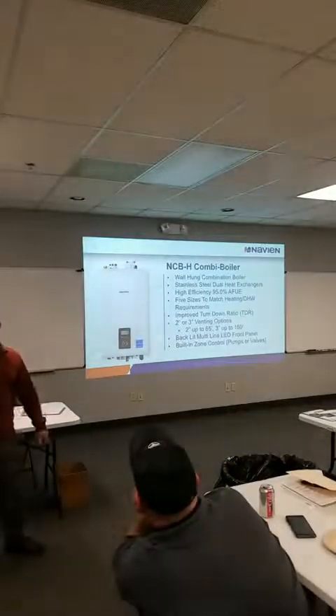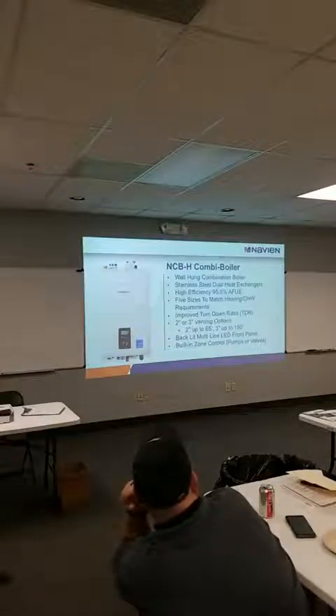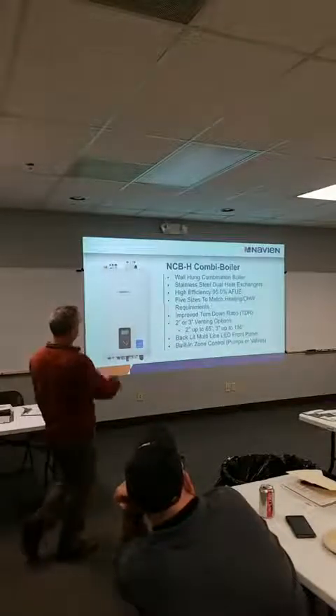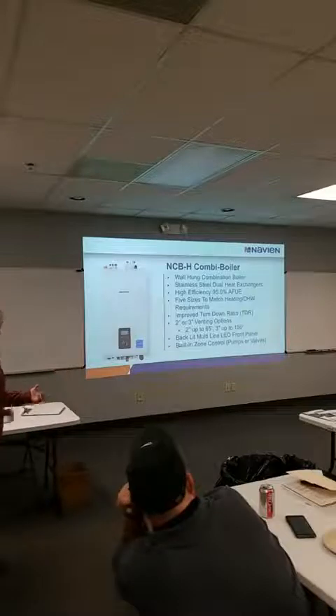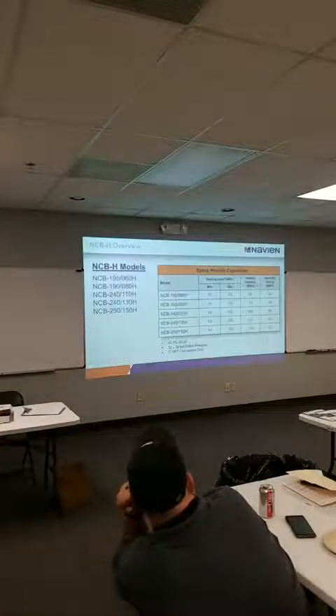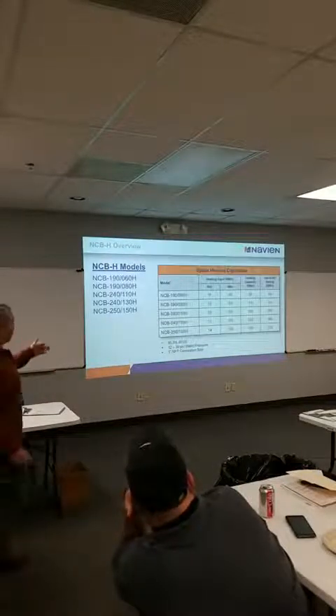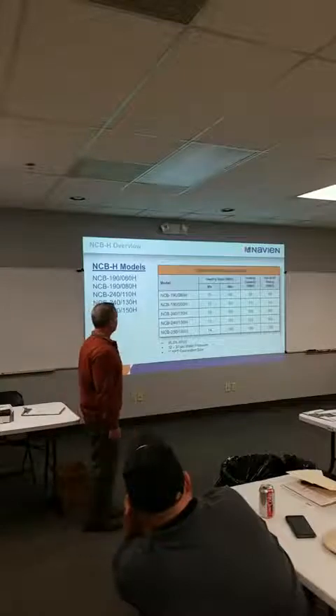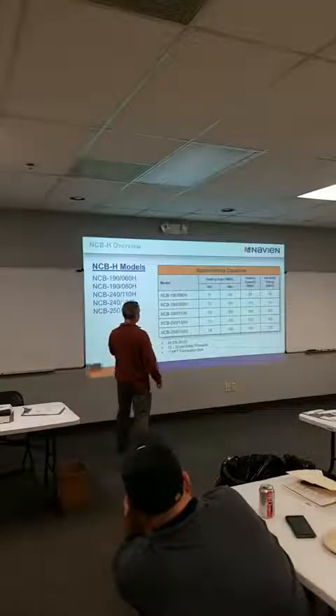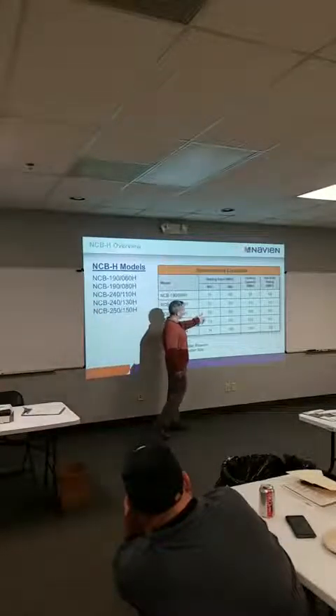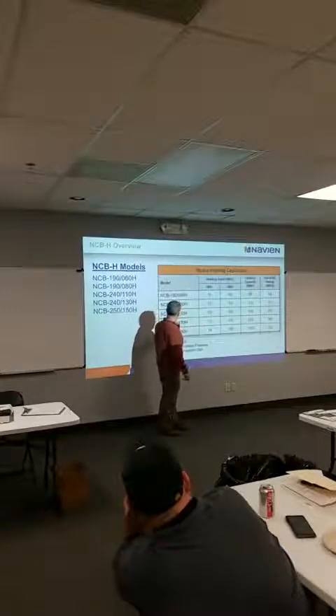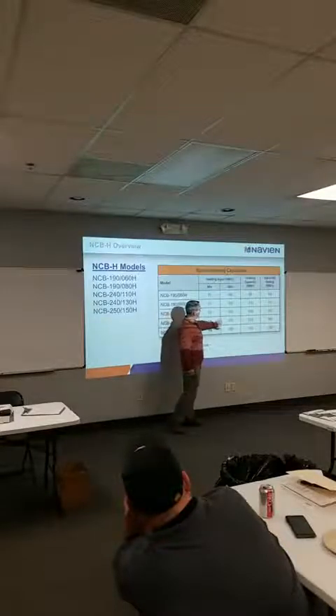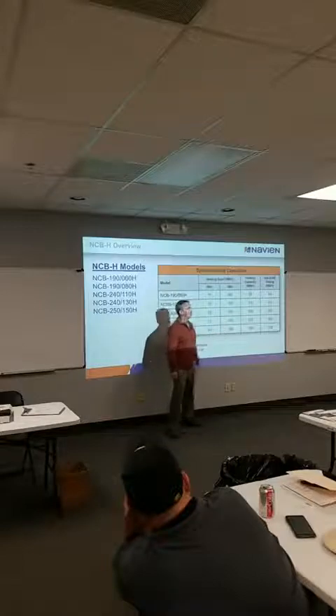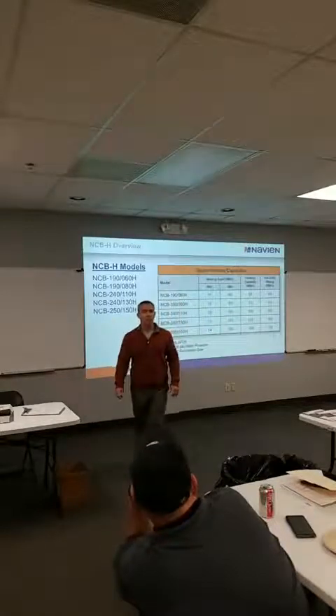And that's bad. So we pushed the 2-inch venting out to 65 feet. But the big deal, the number one thing, is we added a larger size, and we extended the BTUs on this about 10,000 per unit. So the old unit, the 240, would only go to 110. Now it goes to 130, and we've added a 150,000 BTU model in the NCB.